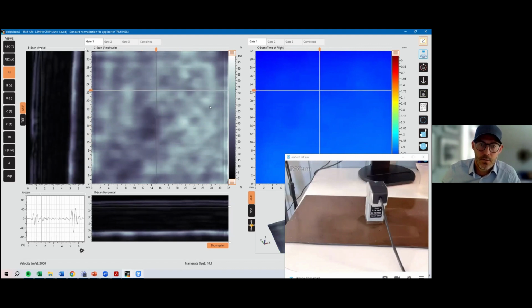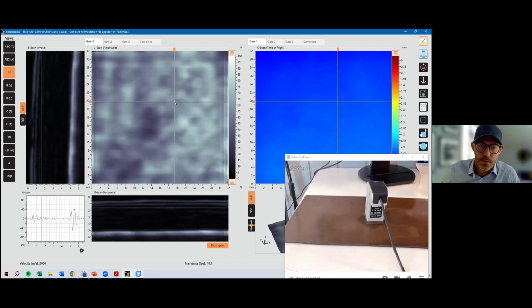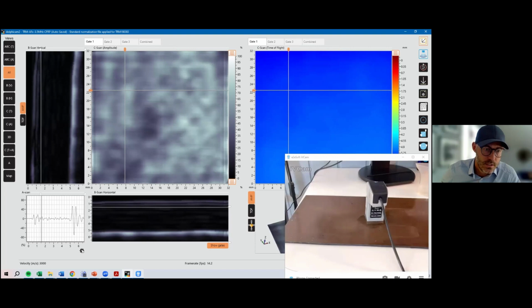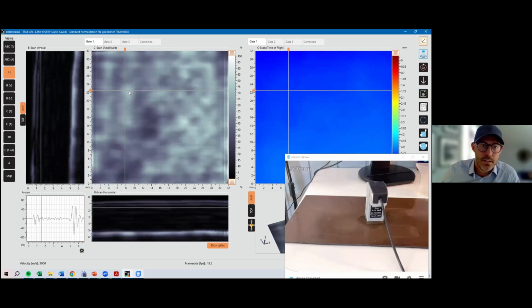And the C scan that you have here, we have a C scan amplitude and a C scan time of flight. This C scan amplitude are values based on the amplitude of this pulse. So you see here, this amplitude is around 50%. And then where I've clicked here is somewhat gray, a little bit light. That's 50% on this scale here. So I have a gray scale here from 0 to 100%. And the color displayed on that point is 50%. If I click on a little bit of a lighter area, I can actually enable that so you can see it. The threshold is almost 80%, and that's the color up here.